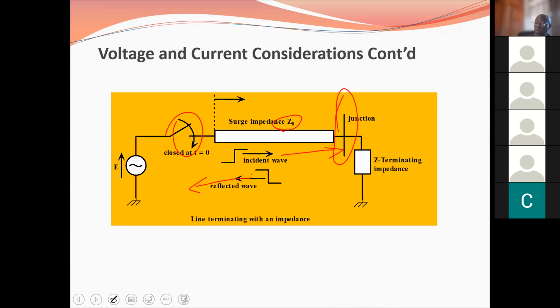But in addition to getting a reflected wave, remember now, not everything will come back to the source. Some will continue to the load, right? Because that's the purpose of the system. The system is to feed this load. So in standard physics, we would say that that is a refracted wave. For our purpose, we're going to call it the transmission. So we'll have reflection coming back at us, but we'll have transmission continuing.